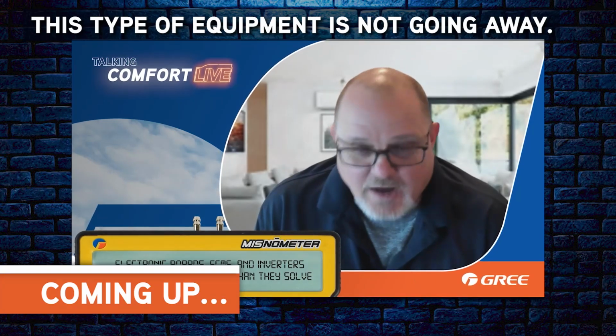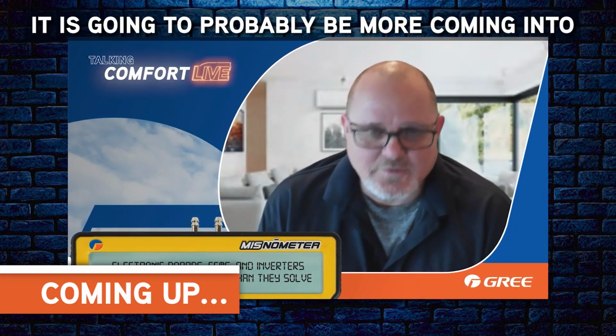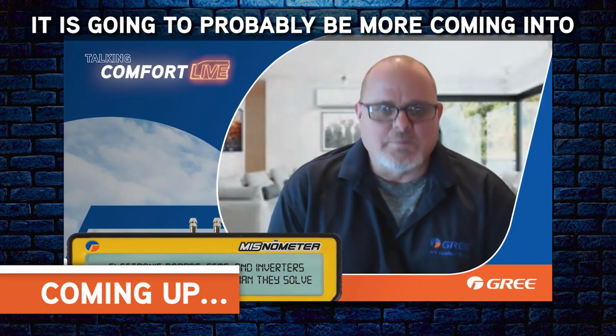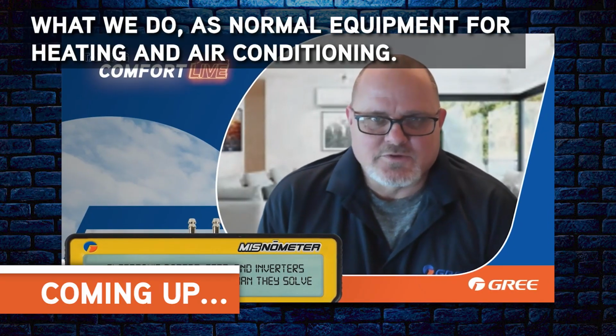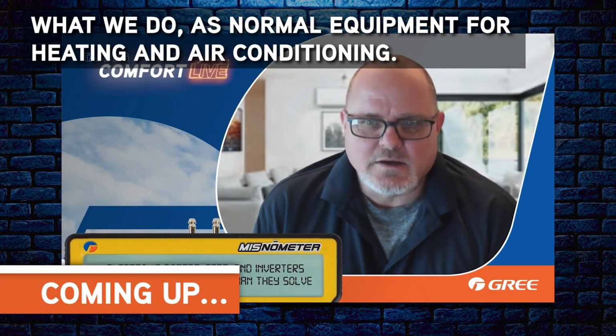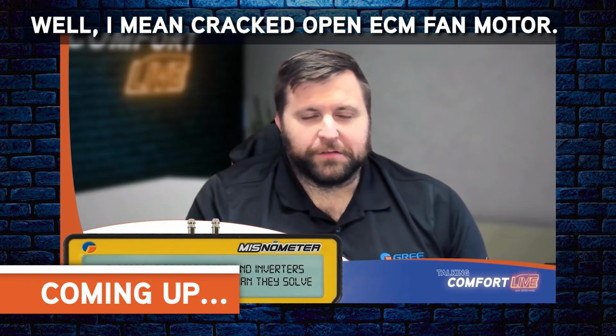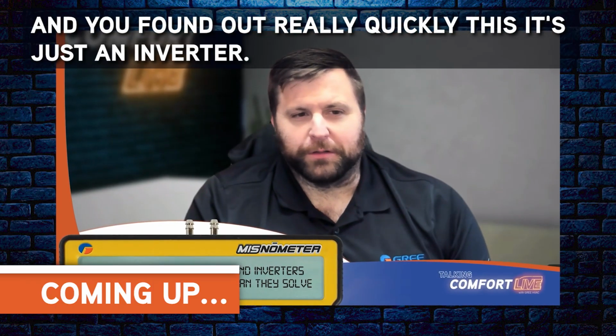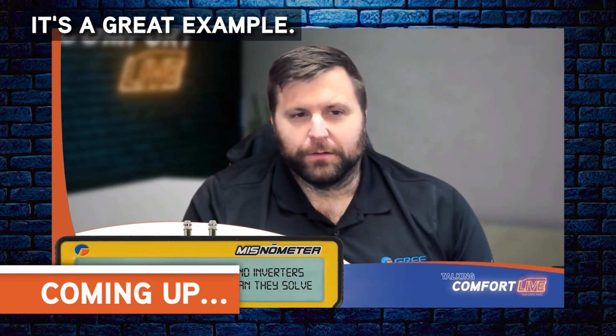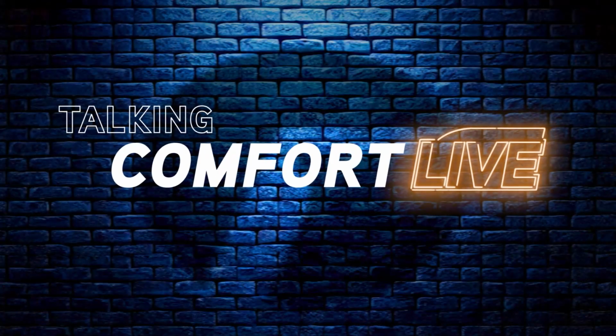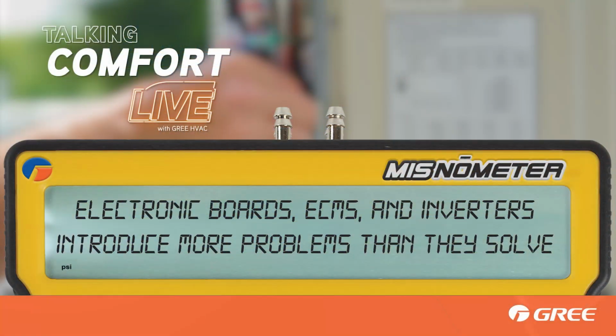This type of equipment is not going away. It is going to probably be more coming into what we do as normal equipment for heating and air conditioning. Well, I mean, crack open an ECM fan motor and you find out really quickly that it's just an inverter. It's a great example. All right, misnomer 1, we've got electronic boards, ECMs, inverters.